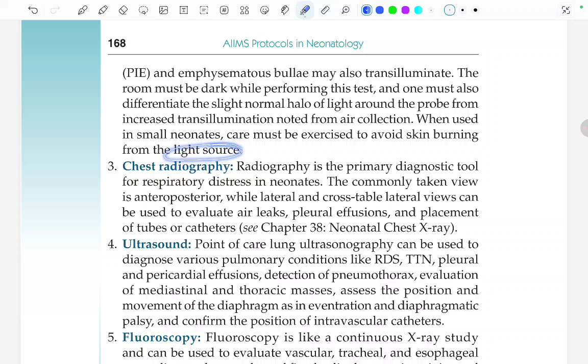So what is written here is that a slight normal halo of light around the probe is normal. We should be able to differentiate it from the increased transillumination which is noted from the air collection. When used in small neonates, care must be exercised to avoid skin burning from the light source. Fine. The light source can even burn the skin, so we should take care and avoid it.